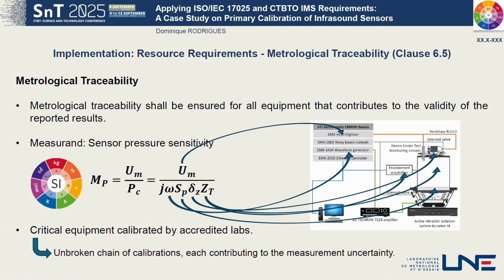And so we have to link this basic unit with the equipment which builds these units. So, for example, the digitizer will provide the link to the volt. The waveform generator will provide the link to the second. The area of the piston will provide the link in part to the meter, etc. So this is very important. The metrological traceability means that all these equipments have to be calibrated, of course, by a service provider that can guarantee this traceability to the international system of units. So it's either an accredited laboratory which operates with ILAC accreditation, or an NMI which has CMCs under CIPM MRA.